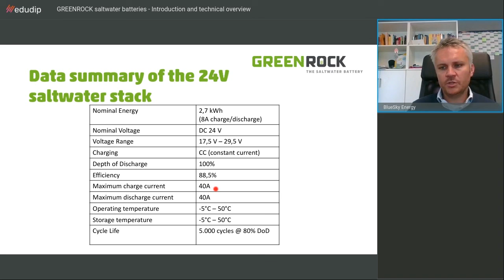We are at 3,500 cycles, assuming we would empty the battery 100% all the time, so making a 100% depth of discharge. And after those 3,500 cycles, we've got a remaining capacity of 70%. On the other hand, when we are using 80% DoD, so not emptying it completely, our cycle life increases to 5,000 cycles, with a remaining capacity of 70% after those 5,000 cycles. When you would only half empty the battery, then we are at 10,000 cycles. And even if we would take only 25% out of the battery all the time, we would be at 20,000 cycles. So as you can see, the cycle discussion always depends on a lot of factors.